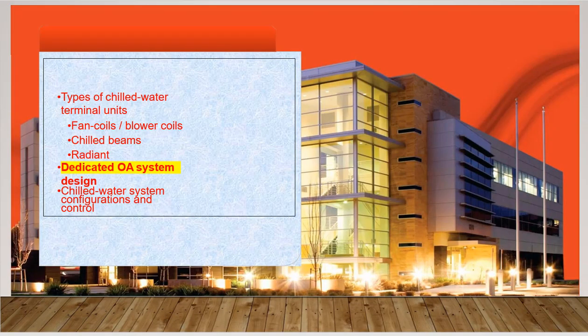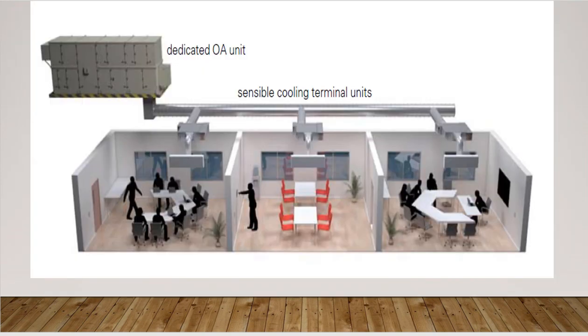As buildings continue to be designed for lower energy use, the resulting reduction in sensible cooling loads presents an economically feasible opportunity for systems that use zone-level sensible-only cooling equipment, such as radiant cooling, chilled beams, and terminal units such as FCUs. The common function of these devices is that they provide sensible cooling only and are not able to provide any dehumidification.